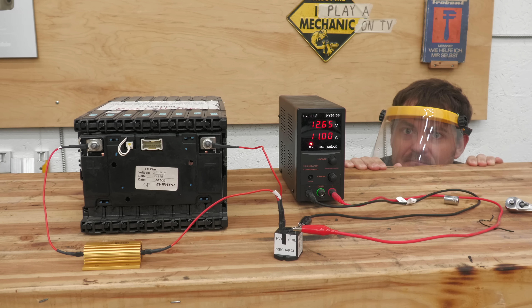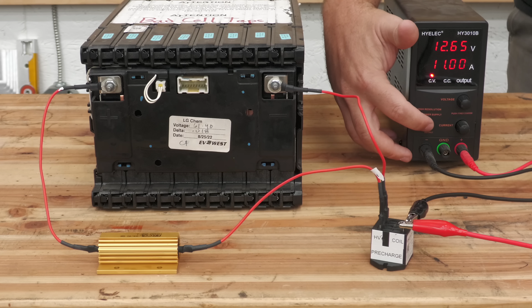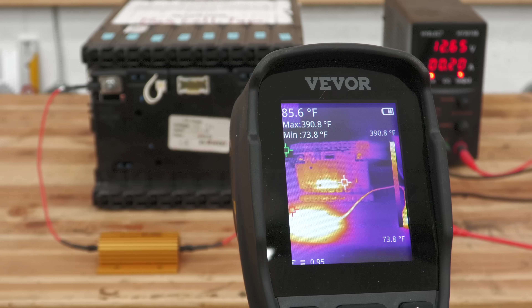To show you what happens when a pre-charge resistor fails, I picked a pre-charge resistor to sacrifice and set up a demonstration. When I turn on this power supply, this contactor will close, and this pre-charge resistor will be shorted across this battery module. Contact. Nothing happened. The voltage of a single module is too low, so the thing I was trying to demonstrate didn't happen, but the resistor did get really hot.